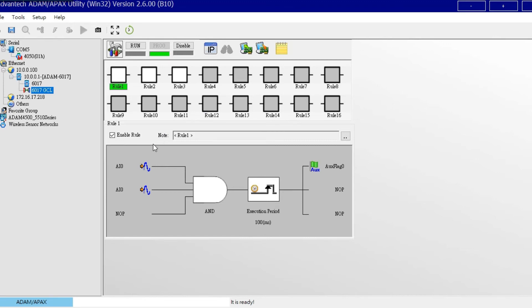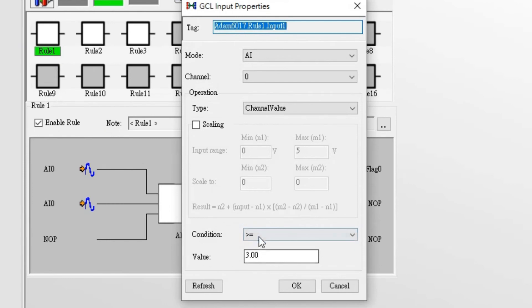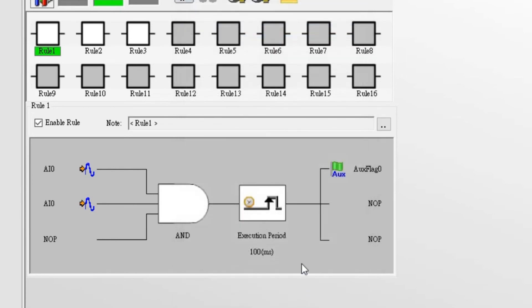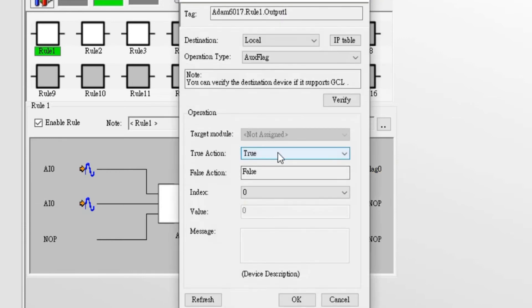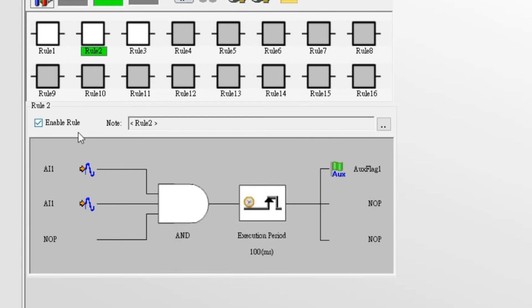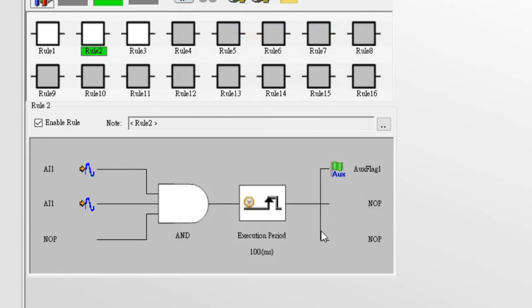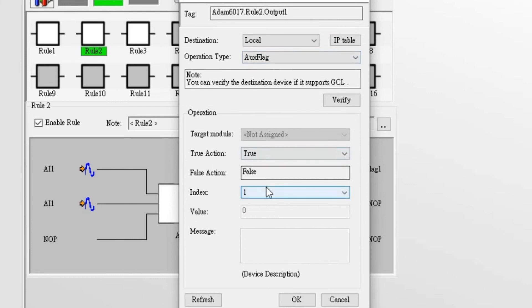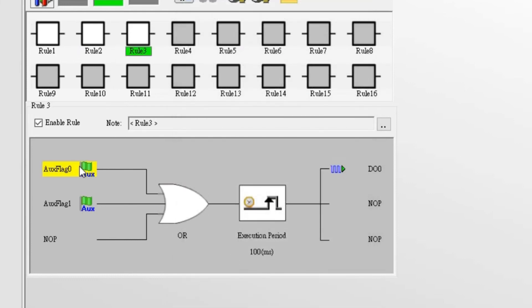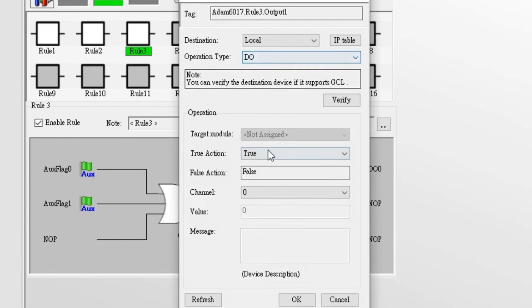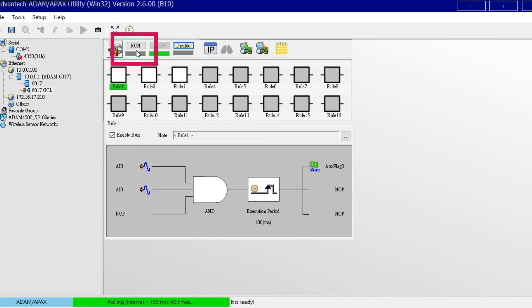In rule 1, set AI0 equal to or greater than 3 and equal to or less than 5 as the input condition, and set aux flag 0 as true for the output. In rule 2, similarly, set AI1 equal to or greater than 3 and equal to or less than 5 as the input condition, and set aux flag 1 as true for the output. In rule 3, the input condition should be aux flag 0 and aux flag 1 — when either aux flag 0 or aux flag 1 is true, it will trigger output DO0 into logic high. Then download the GCL rules to ADAM and run the GCL project.